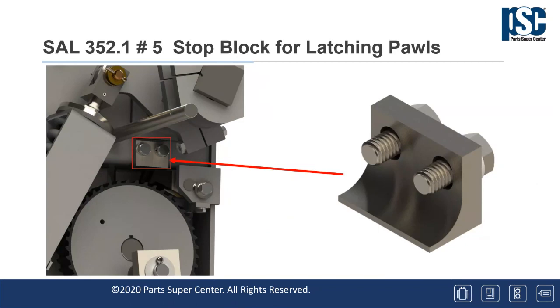Next is number 5 on SAL 352.1, which changed the latching pawl stop block for improved wear characteristics and reliability. The stop block mounting holes were changed to slots to facilitate clearance adjustments between the ratchet wheel and the latching pawls. It also increased the width of the stop block so that both the latching and holding pawls would strike it. This change was introduced into production on breakers manufactured in 1984 and later. Once again, ordering information will be included in the service advisory accompanying these slides.